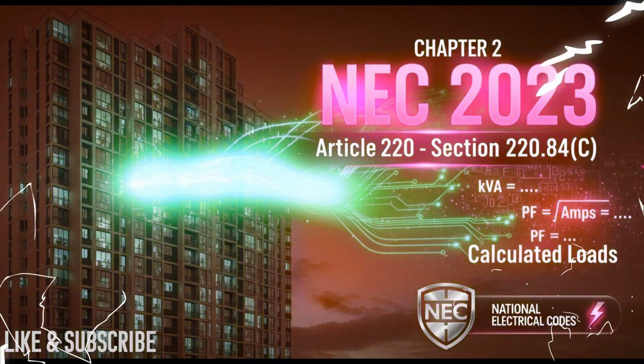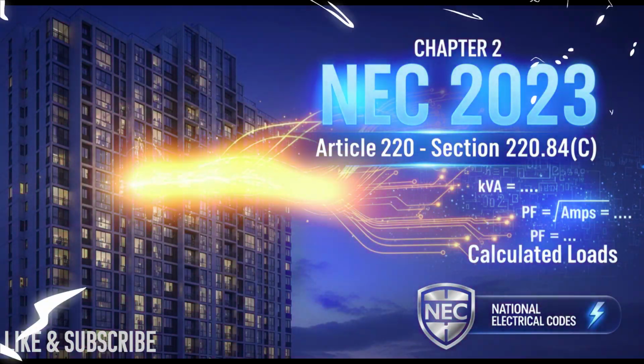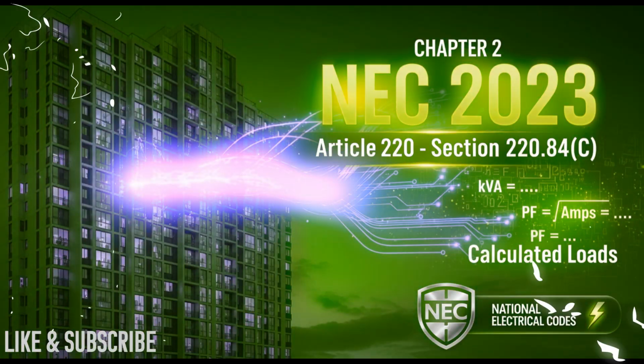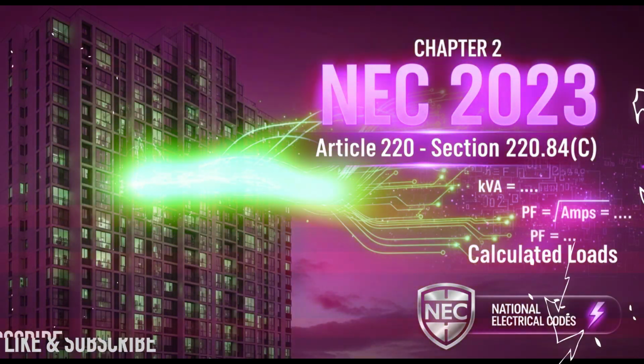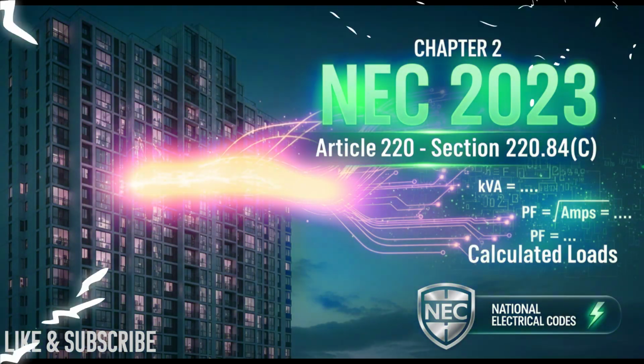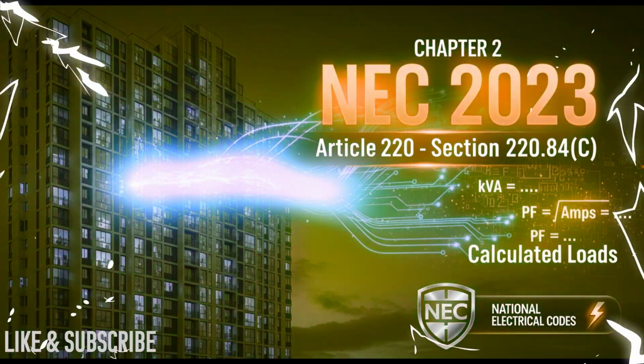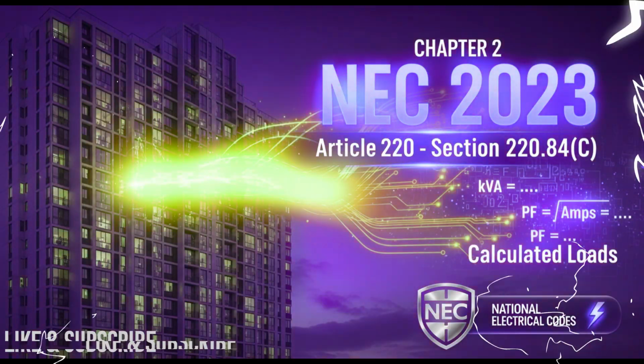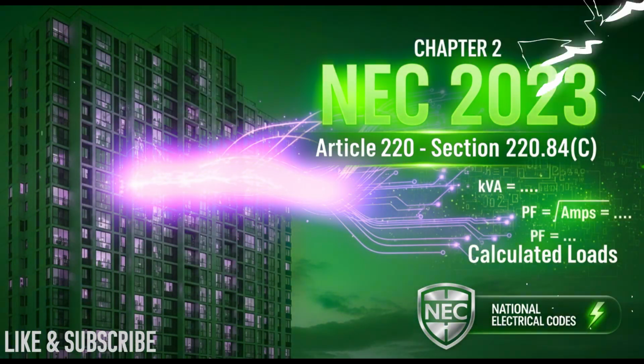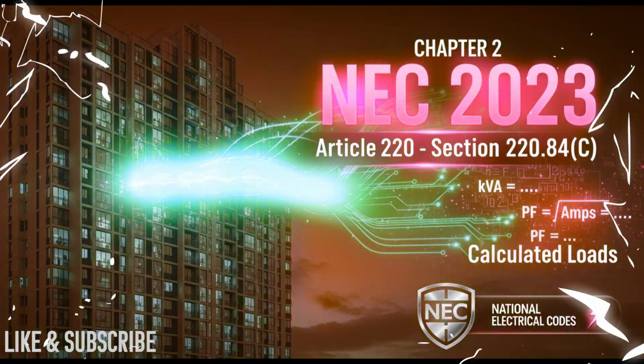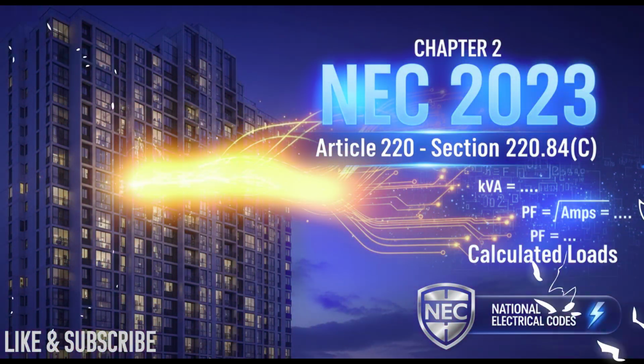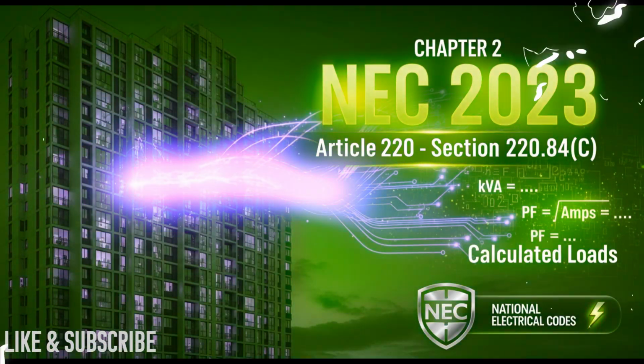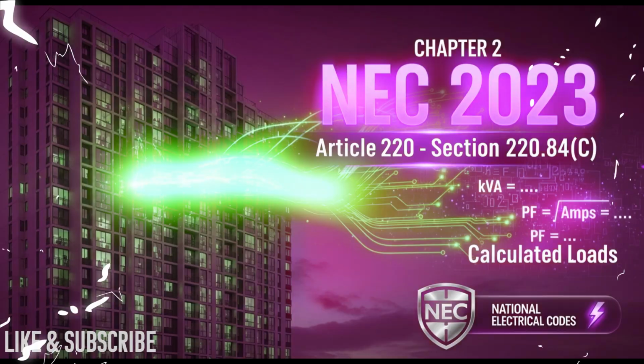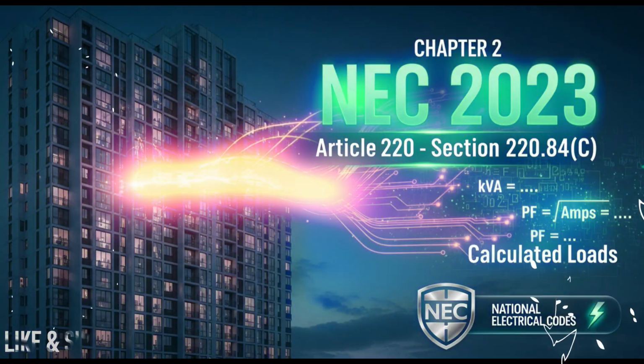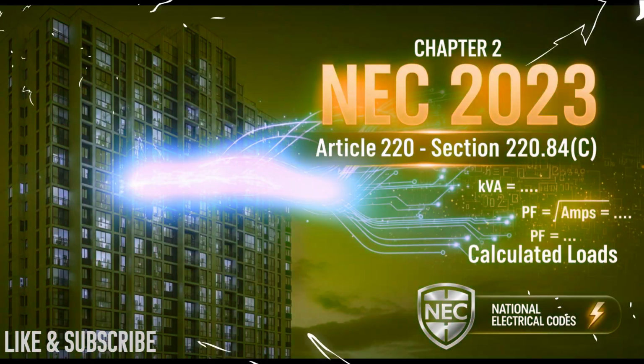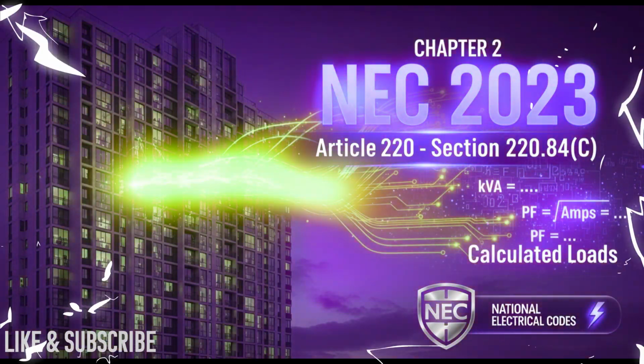You know, it's interesting why the code insists on the nameplate rating. It feels like it's shifting liability almost, ensuring the calculation uses the objective measurable number from the manufacturer. That's a really sharp insight. I think you're spot on. The nameplate is the legally binding number from the maker. It locks the calculation to the actual equipment. So a designer can't just calculate for a small water heater and then let the contractor install a much bigger one later. Exactly. If the calculation used a 4 kW water heater spec, but a 6 kW unit goes in, poof, there goes your safety margin. The nameplate requirement prevents that kind of mismatch, and it anchors the calculation to reality. Okay, so lighting outlets by area.